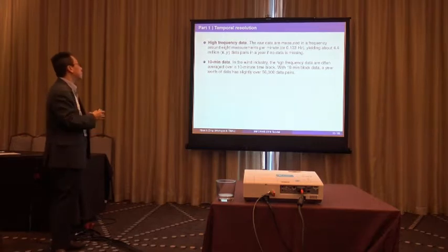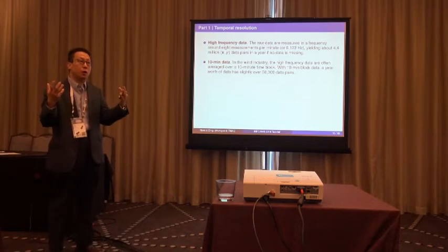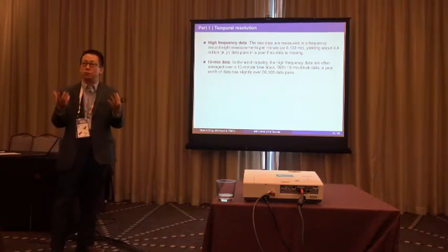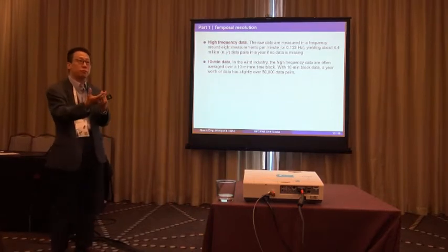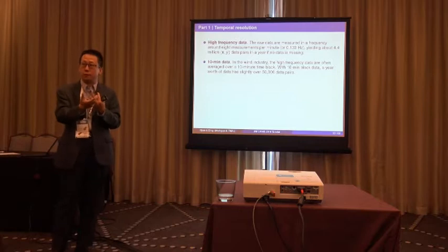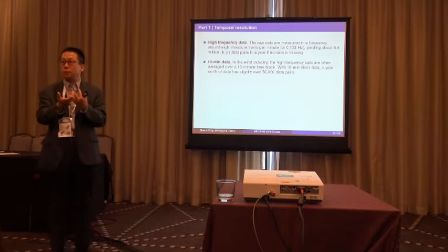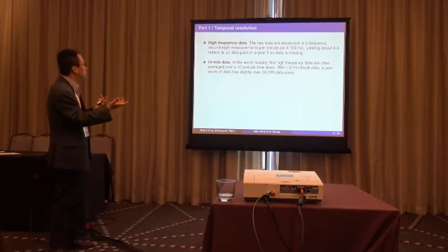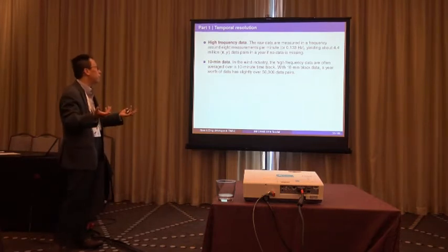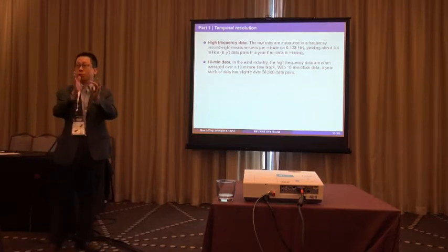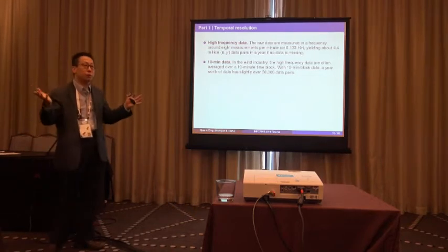And also for the temporal resolution, the original data, which people in industry call historian data, is at high frequency, depending on the sensor capability. It can go up to 1 data point per second, and typically it's about 7 or 8 measurements per minute. If there's no missing data for the whole year, you're going to have about 4.4 million data pairs, X and Y, where Y is the power output or the mechanical load for the whole year.